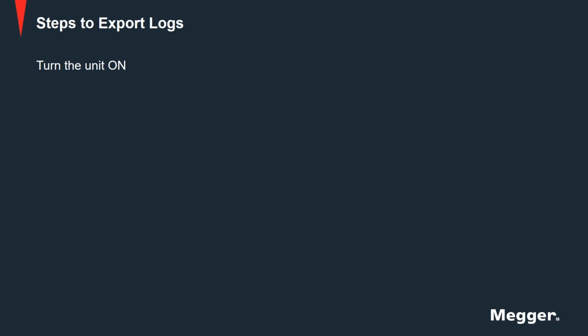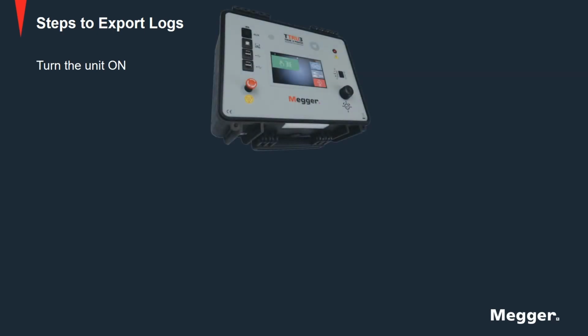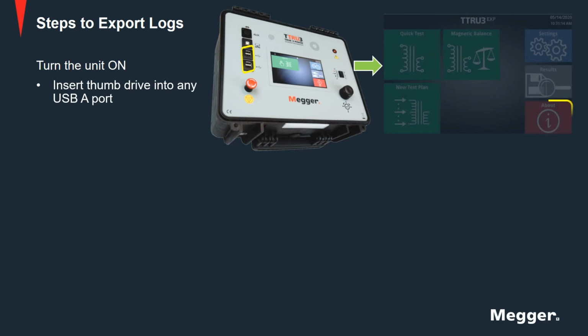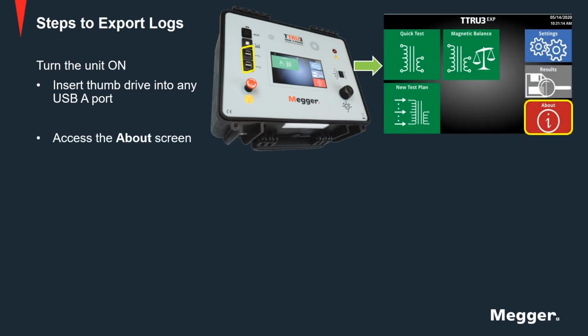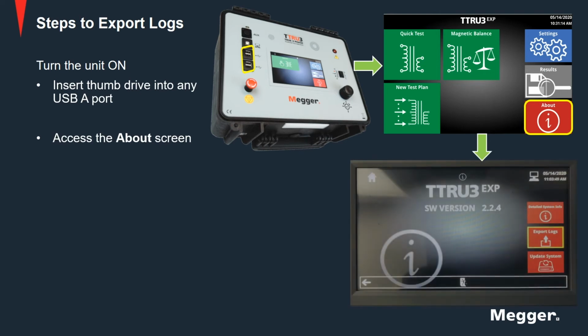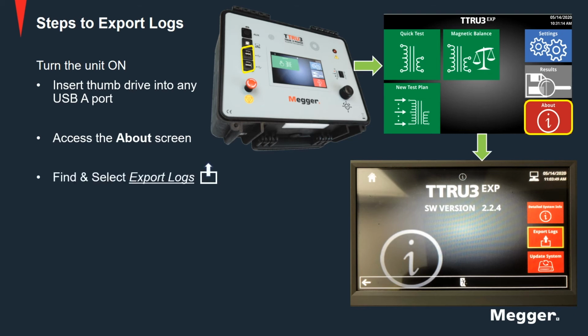At first, you would turn the unit on. After that, you would insert a thumb drive into any USB-A port. After that, you would access the About screen on the TTRU3. Once you select the About screen, a new screen should pop up with options including detailed system information, export logs, and update system. So find and select the export log option.